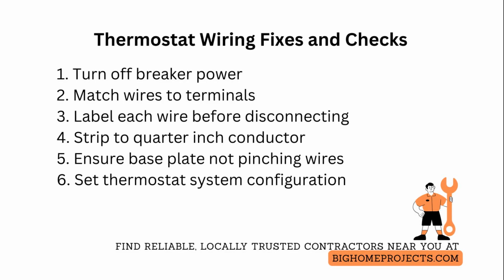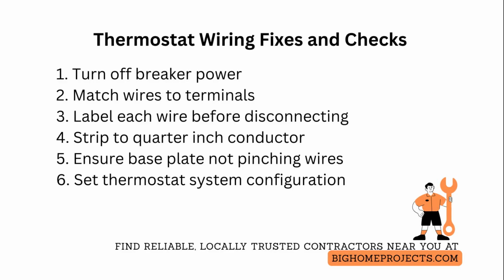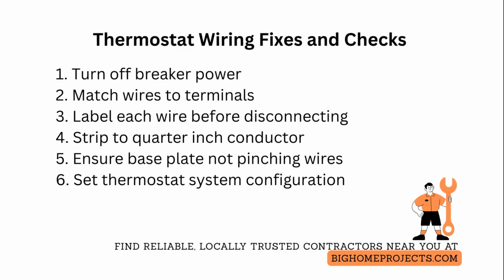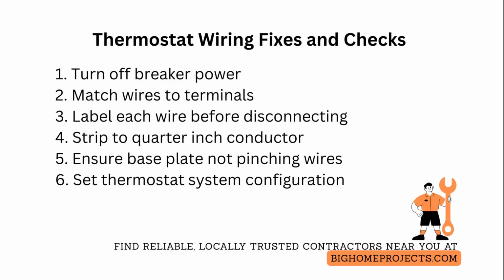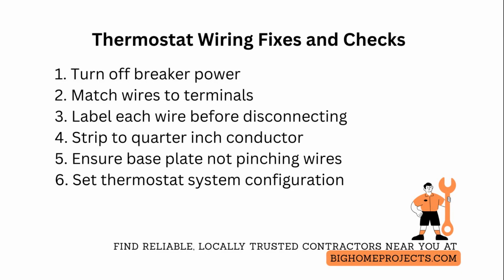After wiring and settings are verified, restore power and observe the control behavior for several minutes while toggling heat and cool. If the unit still runs continuously, isolate the issue by disconnecting the thermostat wires at the furnace or air handler control board and see if the equipment then stops. If it does, the thermostat is at fault. If it does not, the equipment control relay or the furnace air conditioner control board is likely shorted and needs professional service.